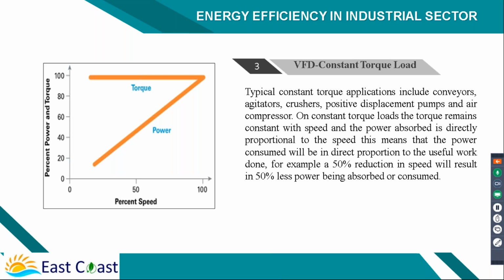So these equipment have almost constant torque requirement, and here the power consumption reduces proportional to the speed. So the reduction in energy consumption is proportional. You may not have the energy savings you'd expect from variable torque load applications. But the point is you can apply VFDs for both variable torque and constant torque if the financial viability is there. Ultimately we look at payback period and return on investment.